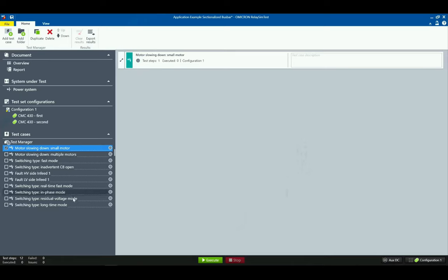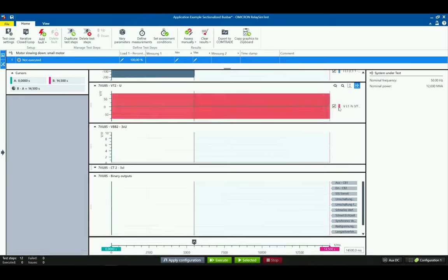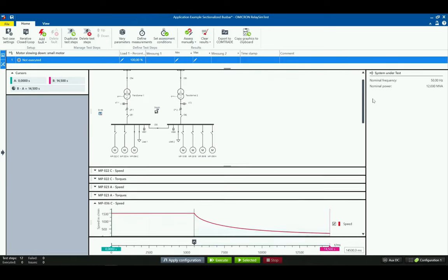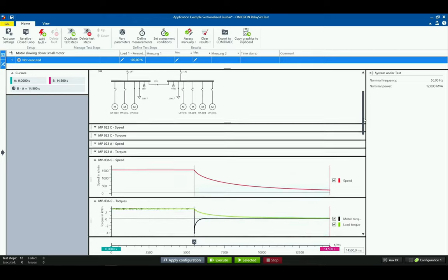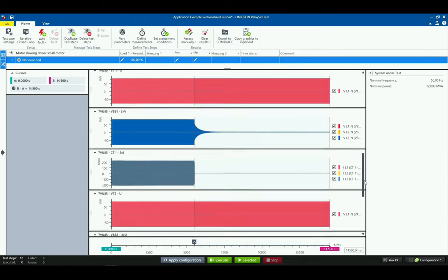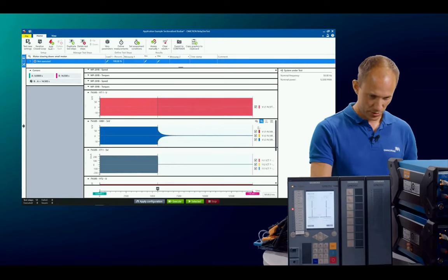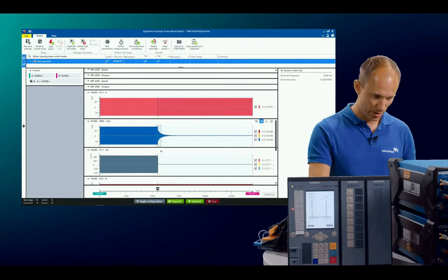Okay, I have prepared quite a few test cases. I will not show all of these test cases, just a few. So one test case would be, for example, a motor slowing down. So I open this test case. Relay, okay, it's working. And you see here, the main focus is of course the power system, but also you see the time axis and the time signals of all the connected CTs and VTs. And you see that this is really a transient simulation and a transient calculation.